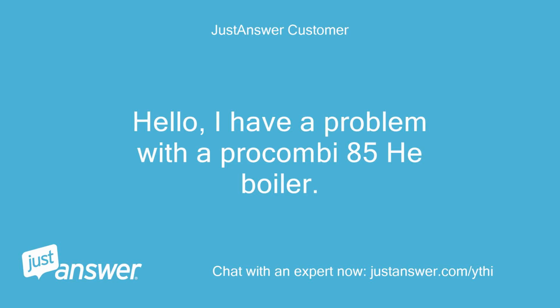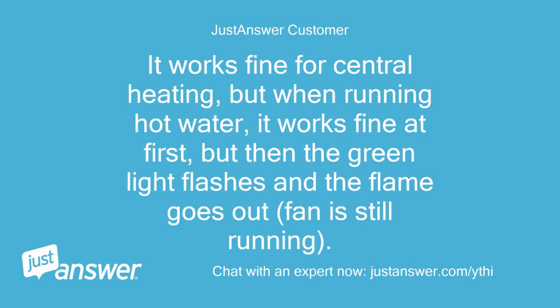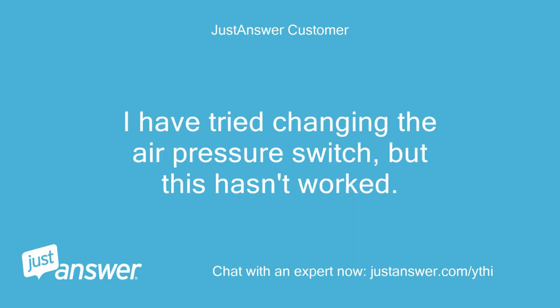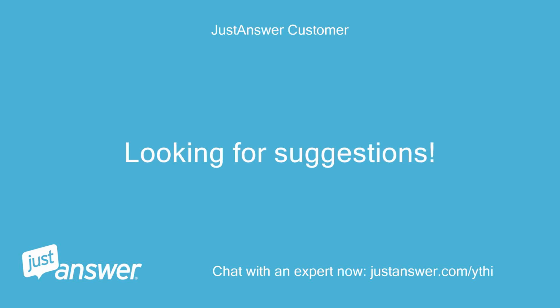Hello, I have a problem with a ProCombi 85 HE boiler. It works fine for central heating, but when running hot water, it works fine at first, but then the green light flashes and the flame goes out, fan is still running. I have tried changing the air pressure switch, but this hasn't worked. Looking for suggestions.